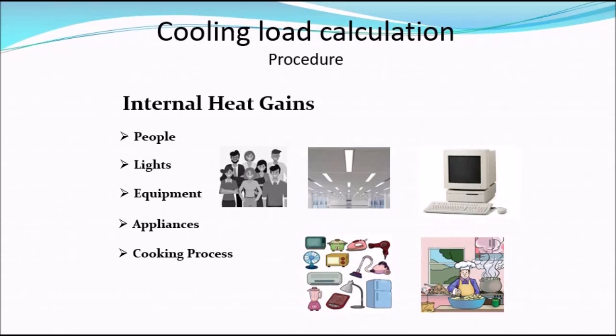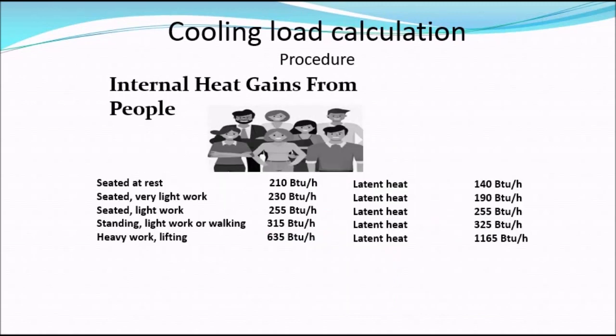The second thing to consider is internal heat gains, which are generated by people, lighting, equipment, appliances, cooking processes, and any equipment or materials brought into the building above the inside design temperature. Let's start with internal heat gains from people. People generate both sensible and latent heat components according to the level of activity. The sensible heat rate increases slightly with higher activity.